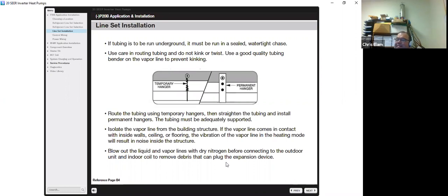If you're using existing lines, I recommend to blow out with dry nitrogen thoroughly. Make sure you get any kind of debris or oil that may be remaining in the existing lines. Any debris or junk can and will end up plugging the expansion devices.